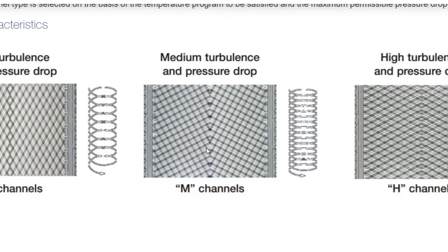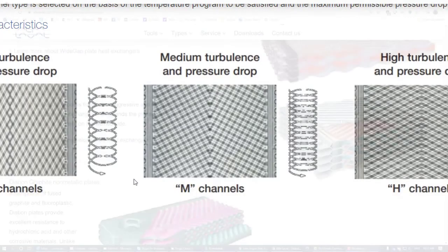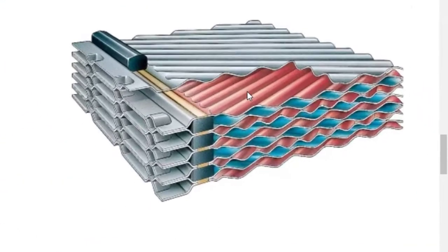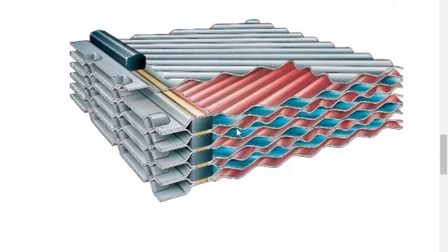In a design we want to use up as much of the allowed pressure drop as possible. It is common that in a plate pack we will use a mix of thetas in order to give the customer the most efficient heat exchanger possible. The placement of high, low, and mixed channels in a plate pack is also a consideration when utilizing the available pressure drop.